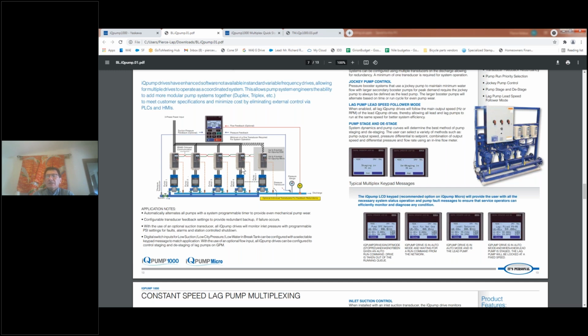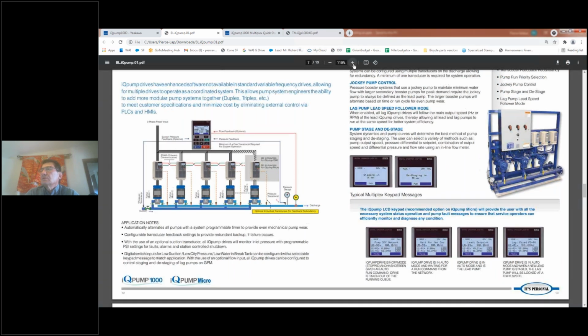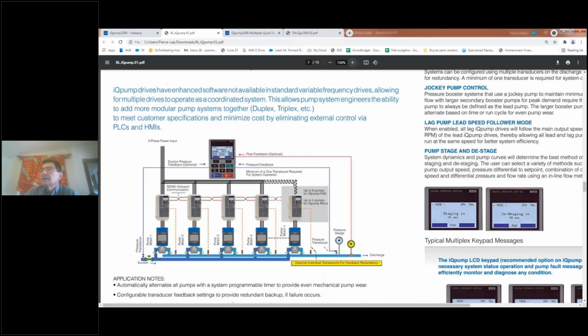How does the multiplex system work? Well, one drive is the master, and one drive receives the signal for pressure, and basically via the network tells the other drives what to do. This is a subnetwork that is peer-to-peer on the Yaskawa drives. It happens to be a Modbus RTU network. It's RS485, super reliable, and certainly fast enough for what we need to do in a multiplexing environment.